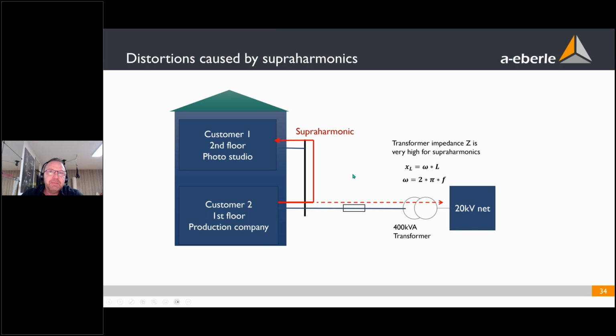If you look at the formula of the impedance of the transformer, you can easily see, if you put in the frequency of 50 hertz and calculate the impedance, or I insert 16,000 hertz, the impedance is huge. And therefore, it's not possible to transfer the supraharmonics from the low voltage to the high voltage grid. So supraharmonics normally will never be a big problem in the medium voltage network, but it means they stay in the low voltage grid. So if this customer is producing the supraharmonics over the current of his frequency converter, over the impedance, we see all the disturbances, 8 and 16 kilohertz, on the voltage.